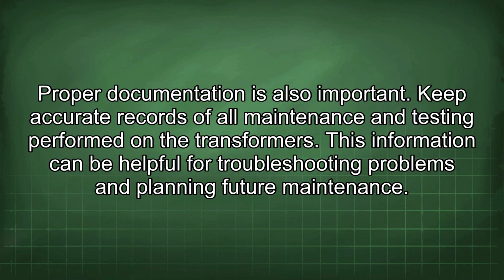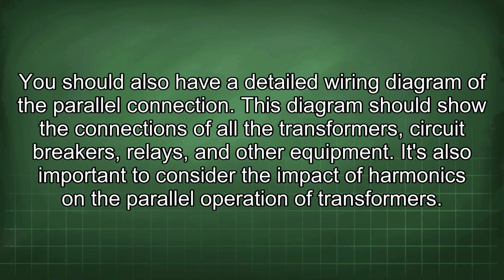Proper documentation is also important. Keep accurate records of all maintenance and testing performed on the transformers. This information can be helpful for troubleshooting problems and planning future maintenance. You should also have a detailed wiring diagram of the parallel connection. This diagram should show the connections of all the transformers, circuit breakers, relays, and other equipment.